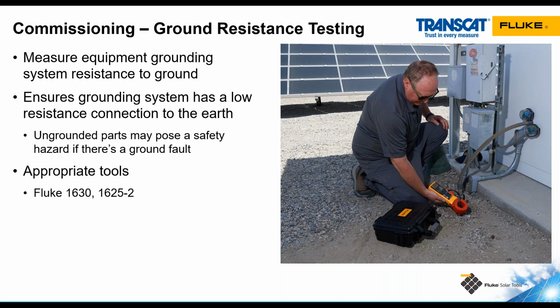We have a suite of tools for doing this type of testing. The 1630 is pictured here, where it is a stakeless test that doesn't need auxiliary ground rods to be able to conduct that test. The 1625-2 comes with some auxiliary ground rods, so that one can do multiple versions of that test in order to ensure that that ground rod has a solid connection to the earth.